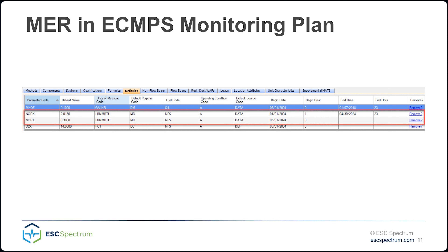In ECMPS 1.0, you will find your current default by going to Monitoring Plan Data and then under Default. Here's an actual screenshot from a customer I've been working with. Their previous value is 2.015 — we have no idea where it came from; it was last done in 2004. So obviously it was time for a new one. This is what their new value is going to be, and you can see that is a major improvement. That's why this is so important.